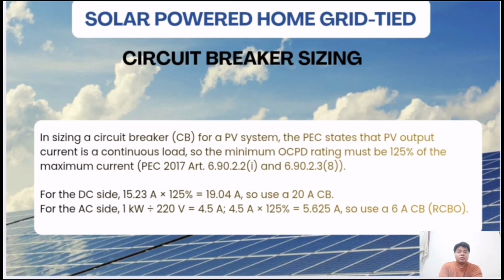Para naman sa AC side, kukunin natin ang current ng inverter gamit ang formula na I equals P over V, kung saan ang P ay inverter power sa watts at V ay system voltage na 220 volts. Sa computation, ang nakuha nating current ay 4.5 amperes. Pagkatapos, i-apply natin ang 125% safety factor. 4.5 times 1.25 equals 5.625 amperes. Dahil dito, pipili rin tayo ng nearest higher standard rating. Kaya ang napili ay 6 ampere RCBO. Ang RCBO ay nagbibigay ng combined protection laban sa overcurrent at earth leakage. Kaya mas ligtas ito gamitin sa AC side ng system.